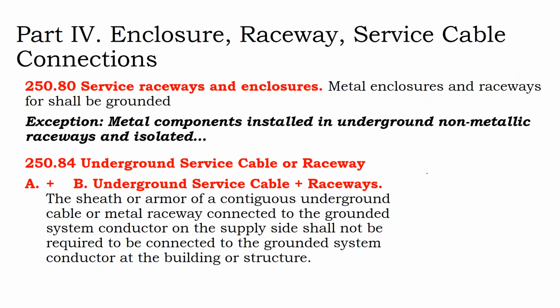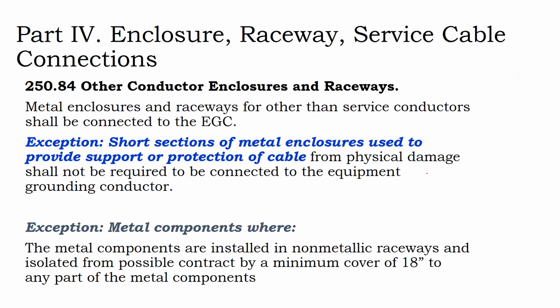So all your metal parts need to be grounded. Metal components that are installed in non-metallic raceways, like a piece of PVC conduit, that are isolated from contact with any other metal parts, don't necessarily have to be grounded. So if you have a splice kit that's listed to fit inside of that shrink wrap splice kit, if it's listed for utility service conductors and feeders, you can put it inside a conduit as long as there's no metal within 18 inches of that connection.